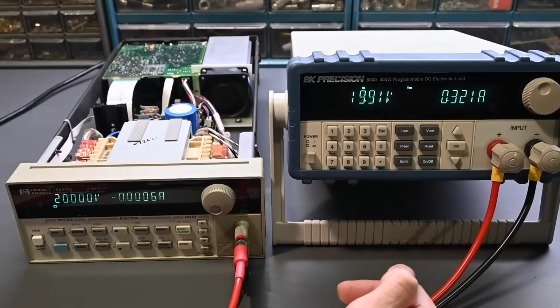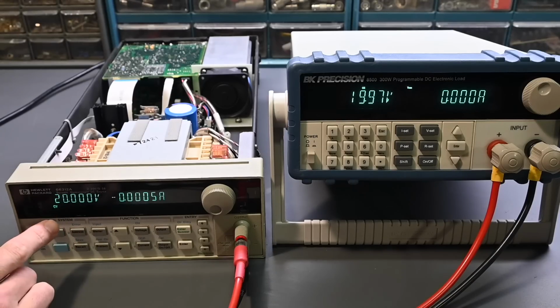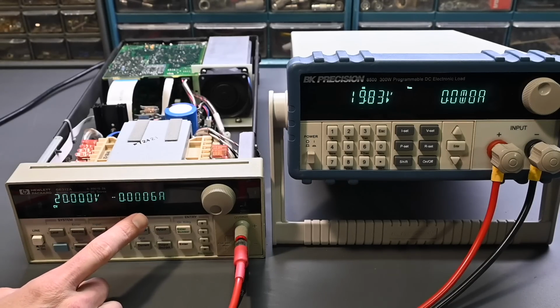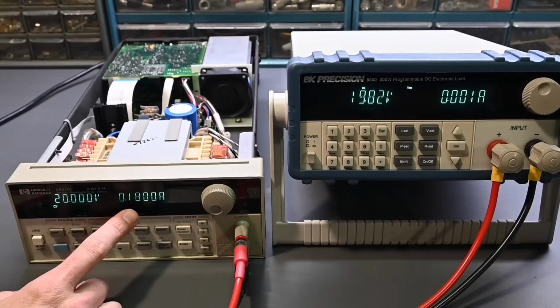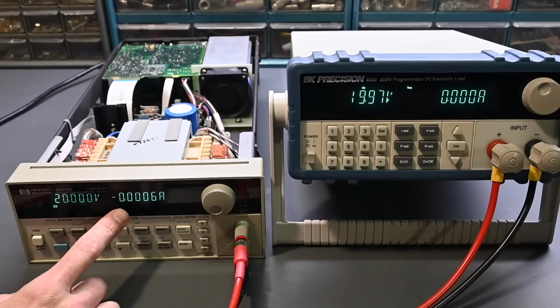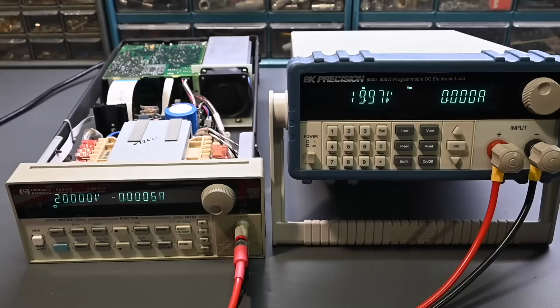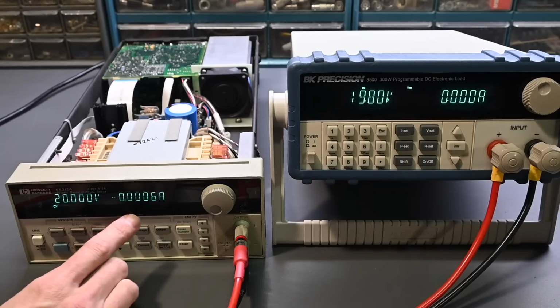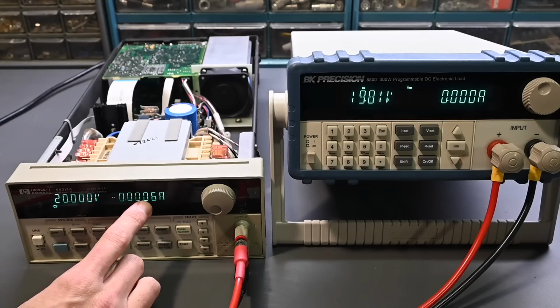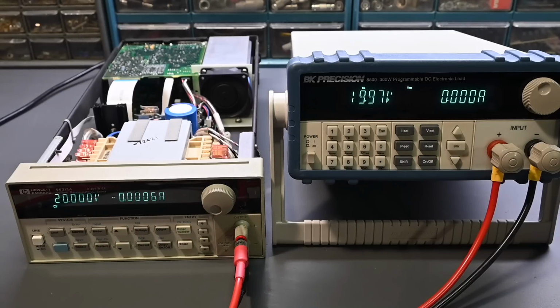That over and over, those two levels from 0 to 1.5 amps, and then that 1.5 amp pulse is happening very, very quickly. Well, if we take a look over here on the power supply, it's 20 volts. You can see the display over here kind of flickers when that 1.5 amps occurs, but it's not a very meaningful display, and it's not indicating the full 1.5 amps. Like there it was 1.3, there it was just 0.3. It's kind of wherever it happens to catch the reading. And that's what a lot of power supplies would end up doing. The current would fluctuate like that, but you really wouldn't see what that true pulse value would be.